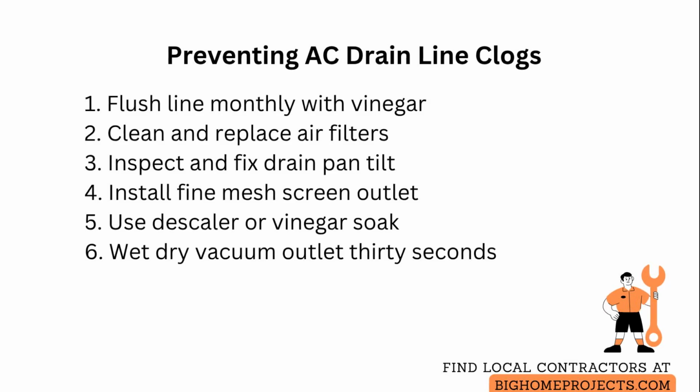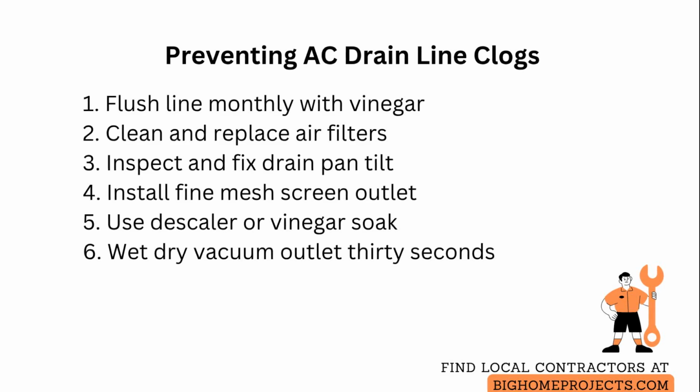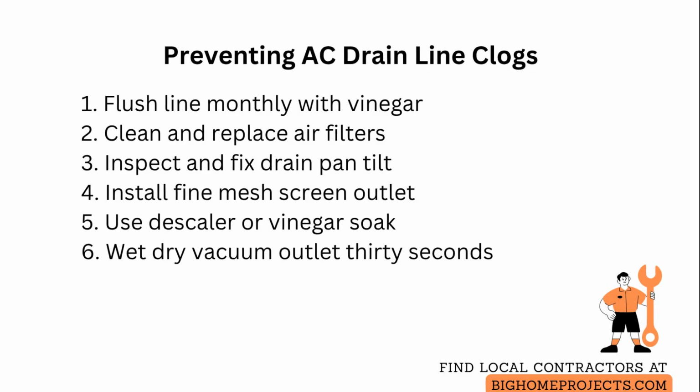Dust and lint enter from the drain pan and evaporator access points, so keep air filters clean and replace them on the manufacturer recommended schedule to reduce particulate load. Mold spores settle where moisture persists. So inspect the drain pan for standing water and tilt or repair the pan if you notice any pooling to prevent stagnation.